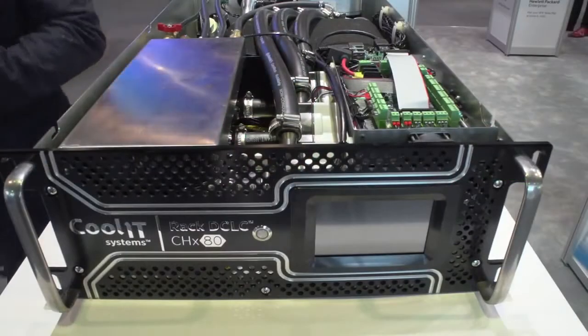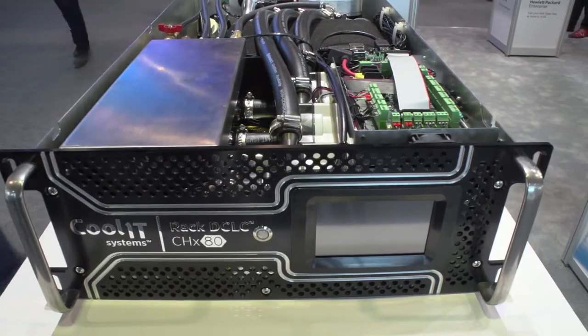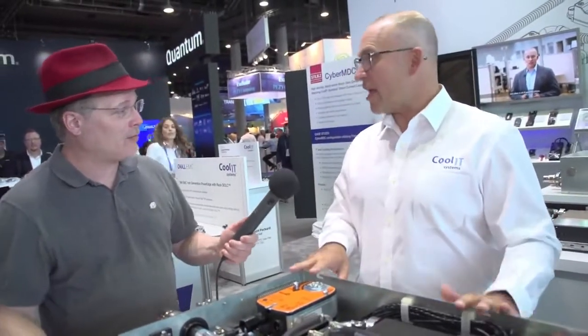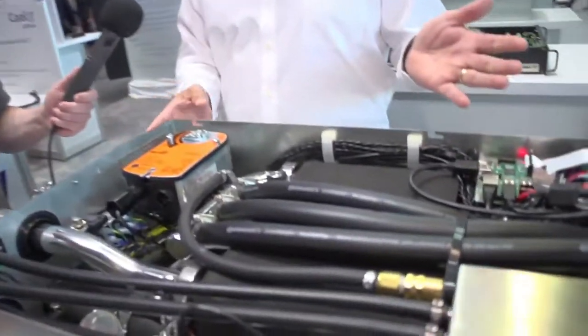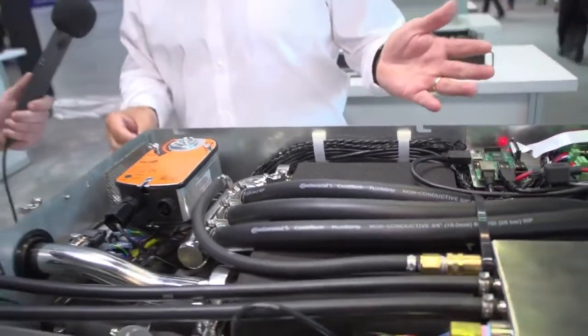You have a 2U 4-node setup, so in a fully populated rack you could have quite a high number of nodes, right? You could potentially have as many as 38 nodes times 2. So you could do 80 kilowatts in a single rack with this? 80 kilowatts and 80 nodes. This could actually support up to 120 nodes.